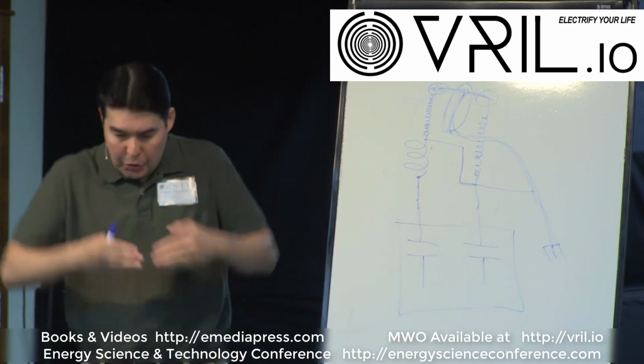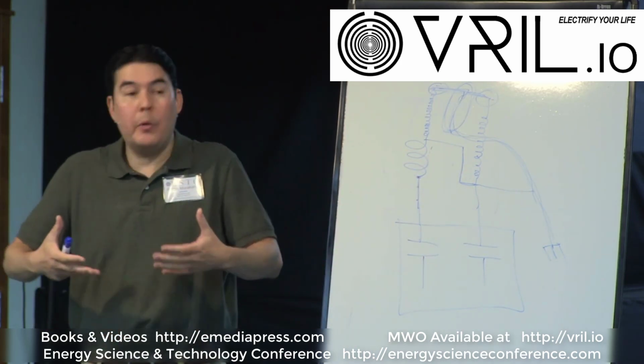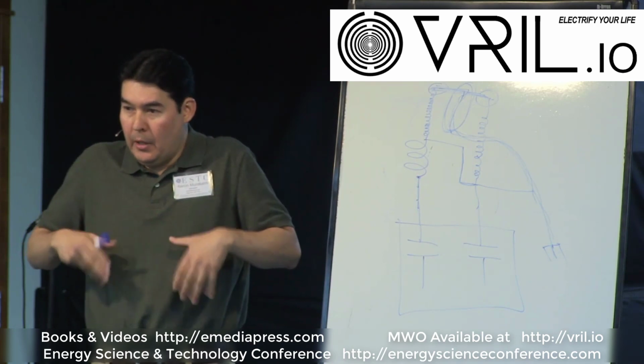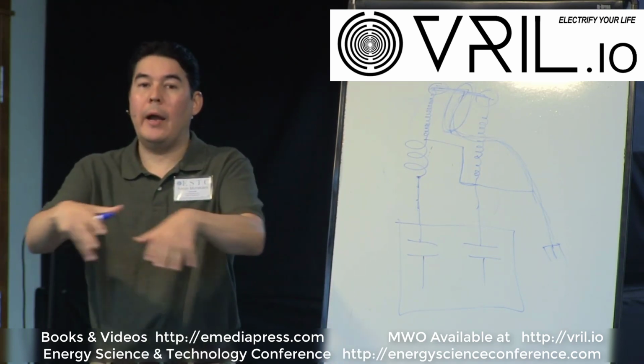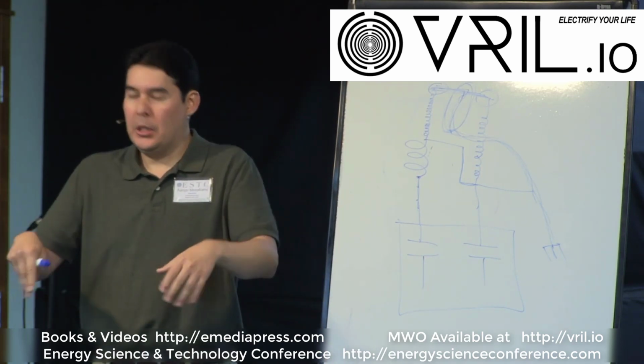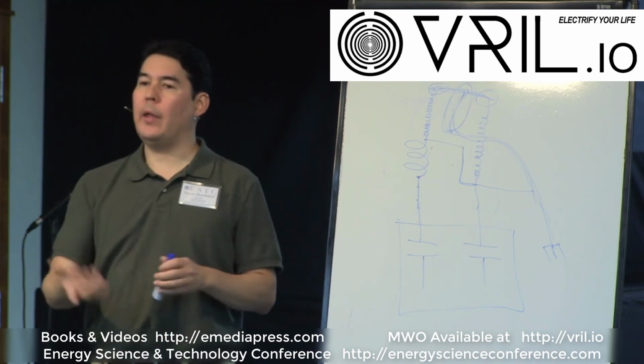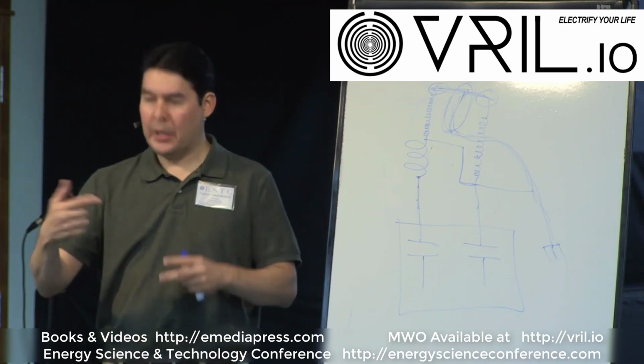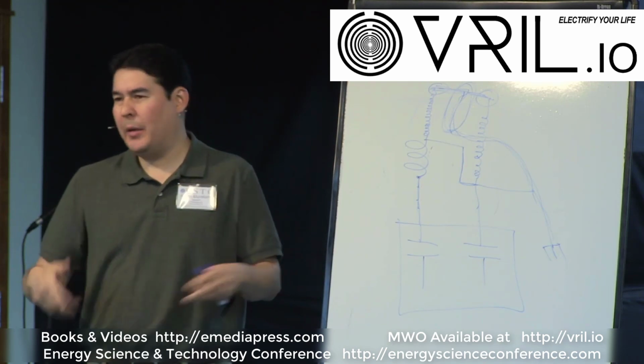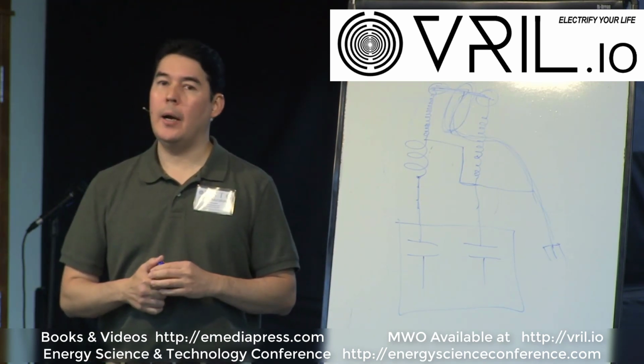Inside that case, there's a divider plate. All the low frequency, low voltage stuff is on one side. On the other side of the plate is all the high frequency, high voltage stuff. Because if you don't isolate them from each other, all that RF can feed into that low voltage winding.